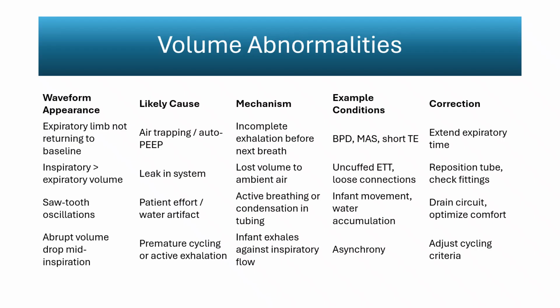An abrupt drop in volume mid-inspiration occurs when the infant actively exhales against the ventilator or when the breath cycles prematurely. The infant's effort briefly reverses flow, breaking the normal upward trajectory of the volume limb. This finding reflects asynchrony, often driven by discomfort, inappropriate inspiratory time, or unexpected exhalation reflexes. Adjusting cycling criteria reduces mid-breath flow reversal and stabilizes delivered volume.